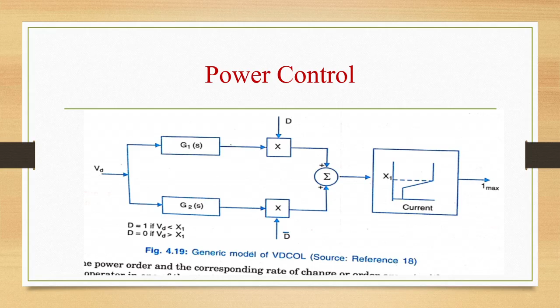Auxiliary controller is designed to provide power modulation for frequency control or stabilization of AC systems. The input signal is derived from frequency or other signals. Then we have seen higher level controllers, that is, power in a DC link can be controlled in response to quantities derived from the AC system in order to improve the security of the overall system. This is achieved by additional power order derived from an emergency power controller or auxiliary controller.